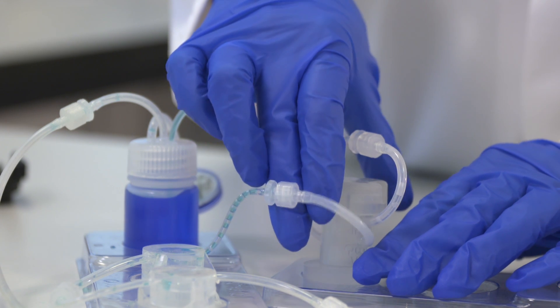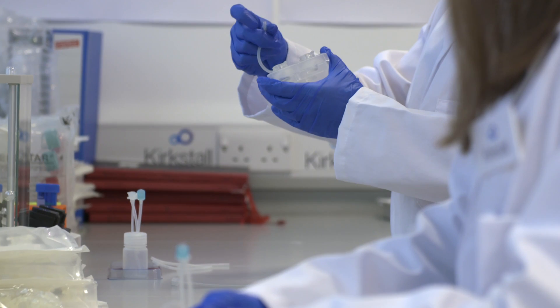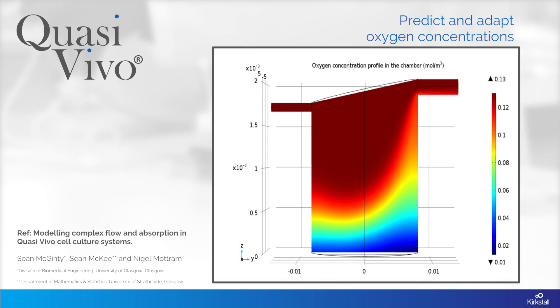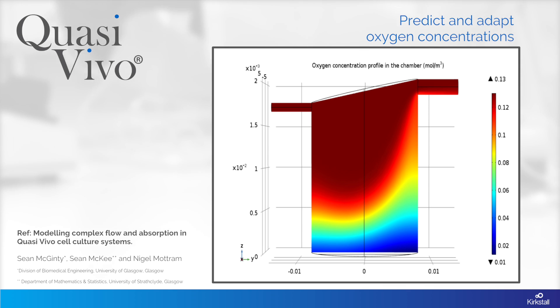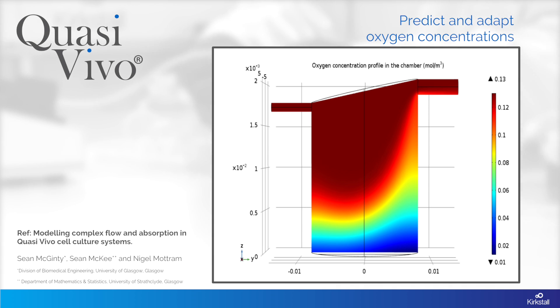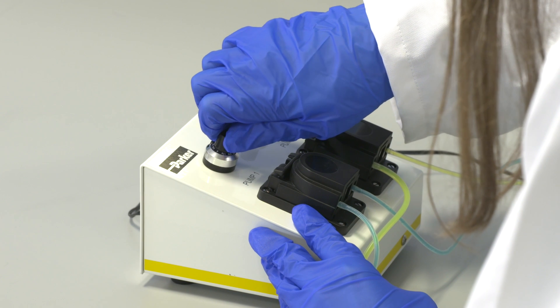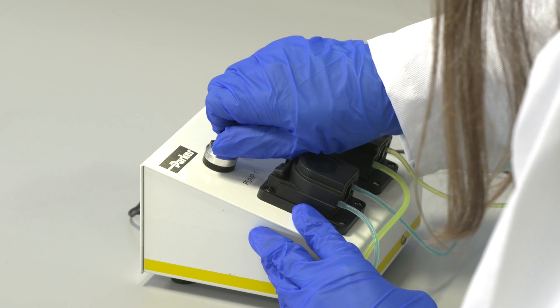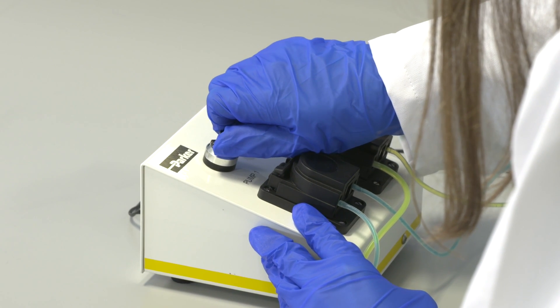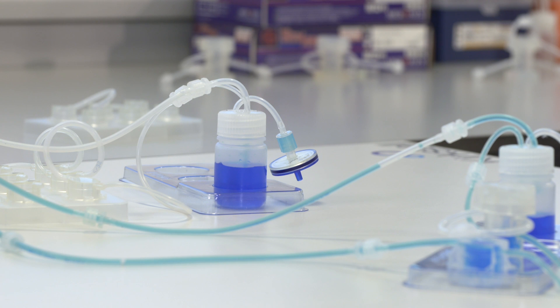The Quasivivo systems were designed to provide metabolically active cells with ideal oxygen concentrations. Furthermore, oxygen gradients within the chamber can be predicted using modelling software and adapted by using inserts to alter the depth of the chambers. The flow rate of the media is easily adapted by changing the settings on your peristaltic pump to ensure that the media perfuses cells at the correct level.